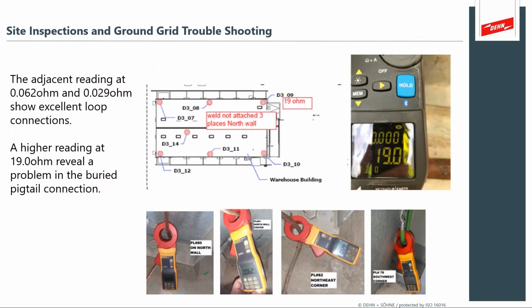And what you can get from the data from an inspection system like that is it'll show you where the problems are. If you're measuring 0.062 and 0.029 around the perimeter of a building at its pigtails, and then you find a pigtail connection that's orders of magnitude higher, that tells you that the buried connection has a problem.